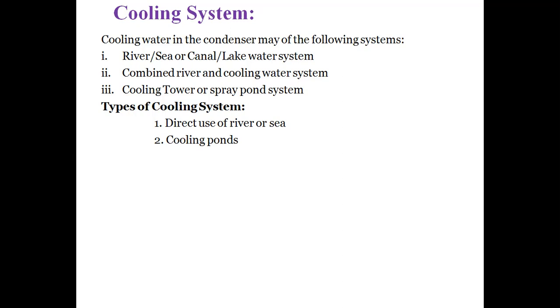This water is circulating as a cooling system. So the cooling water requirement in an open system is about 50 times the flow of the steam to the condenser. Even with the closed cooling system using cooling towers, the requirement for cooling water is also considerable, about 5 to 8 kgs per kilowatt hour.